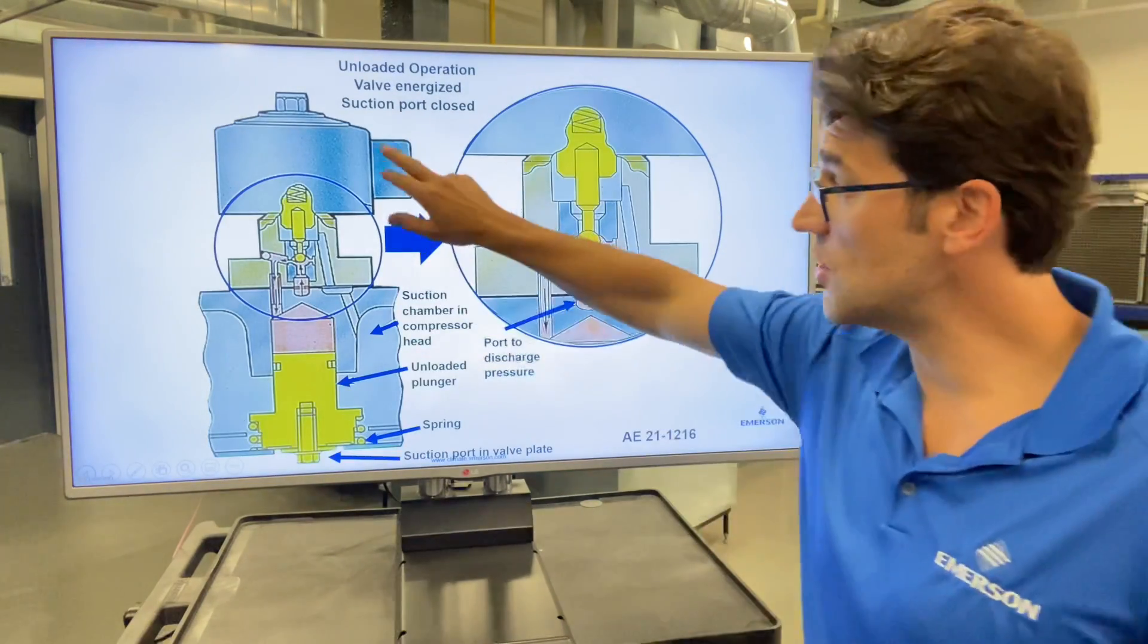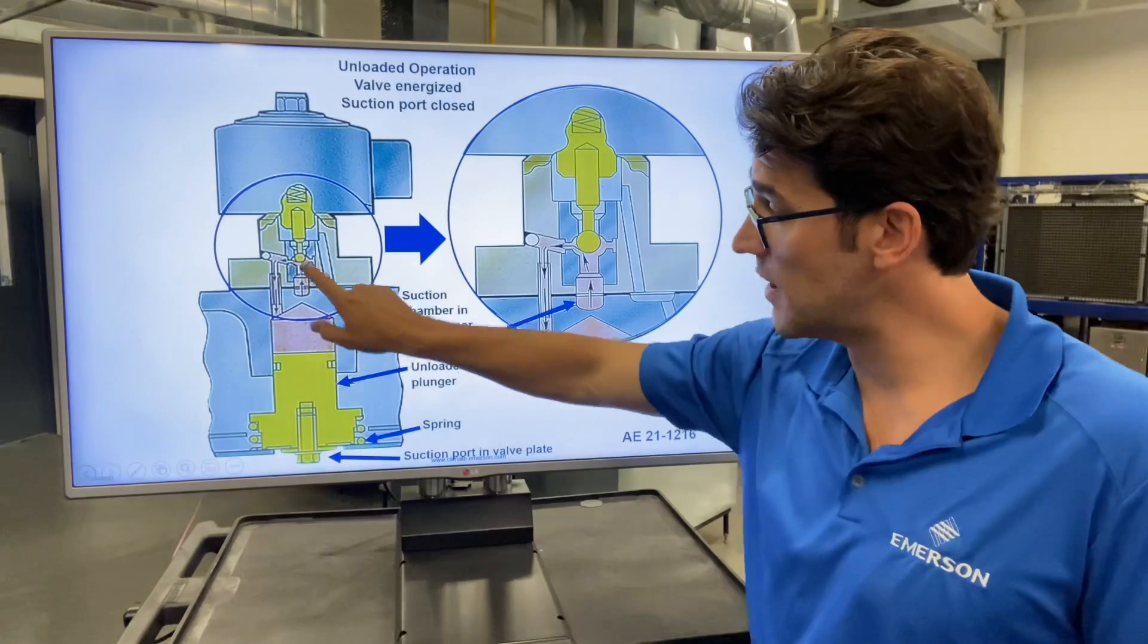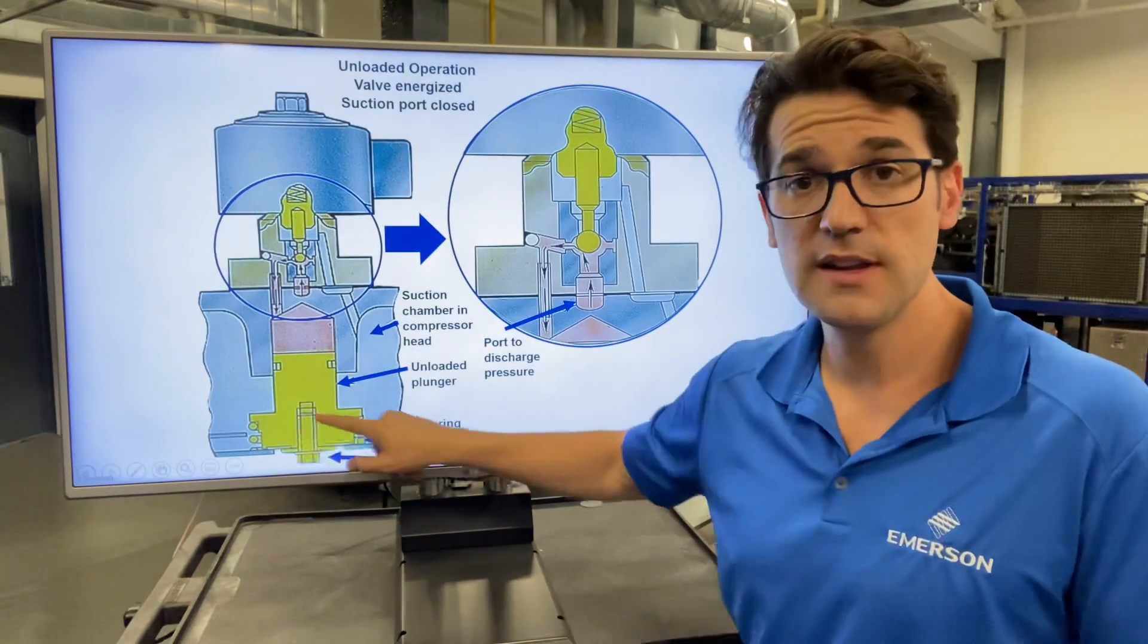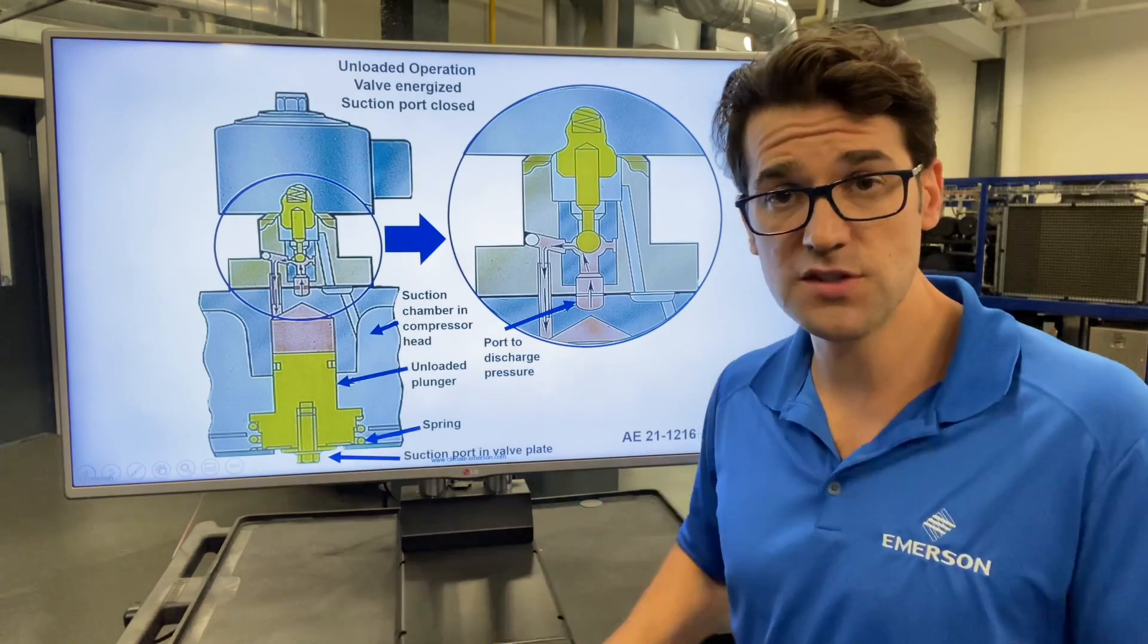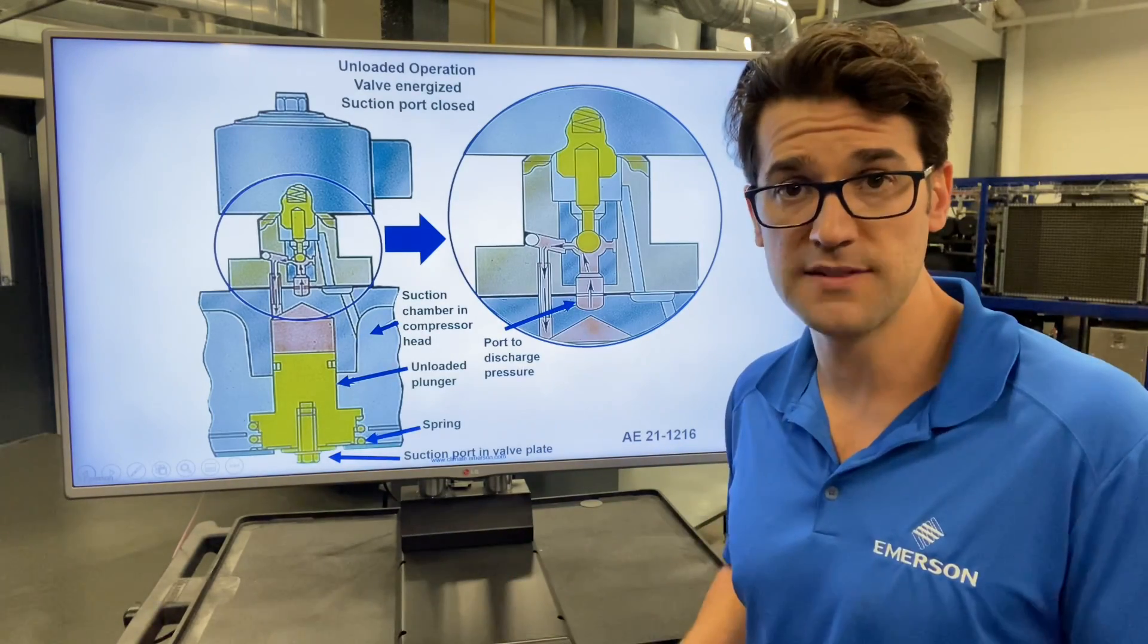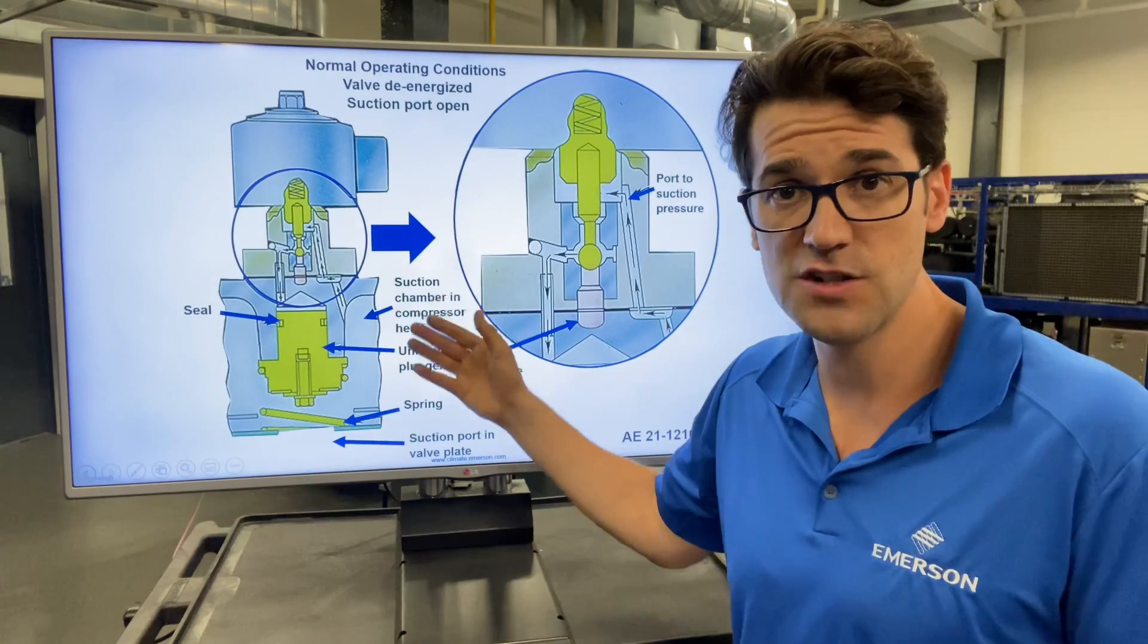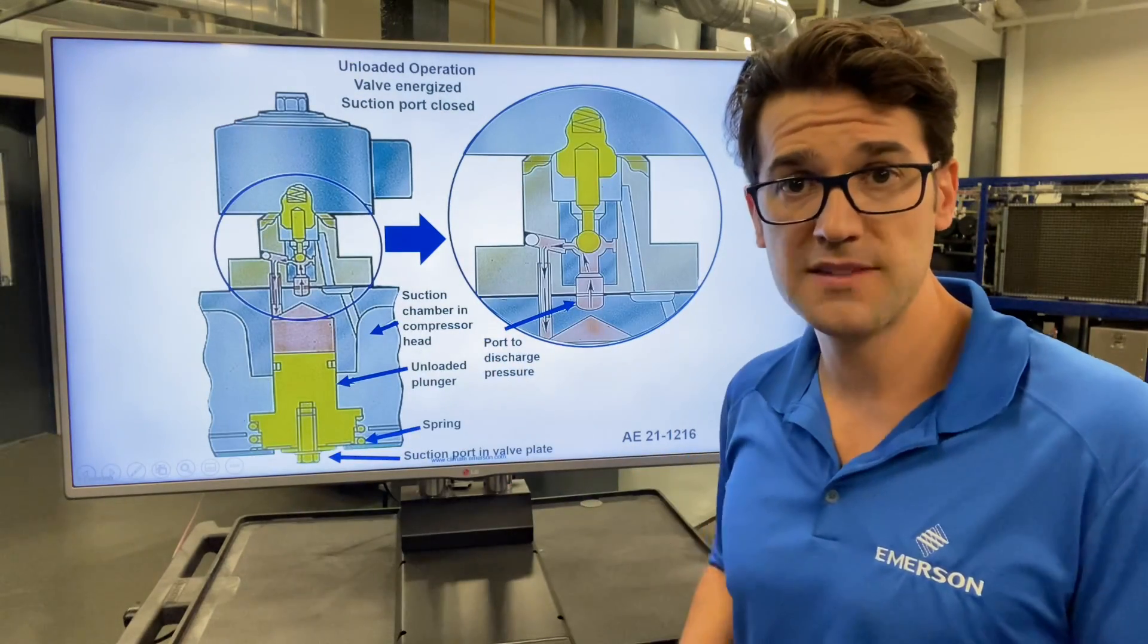But when this solenoid energizes, it opens up this discharge port and puts pressure down on this plunger and closes it. Closes the suction so there's no compression. Now you're at 50% capacity. 100% capacity de-energized, 50% capacity when energized.